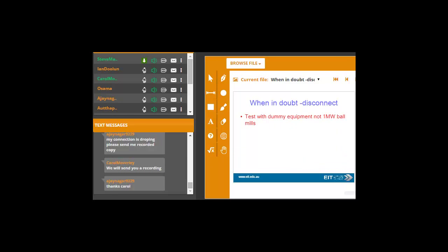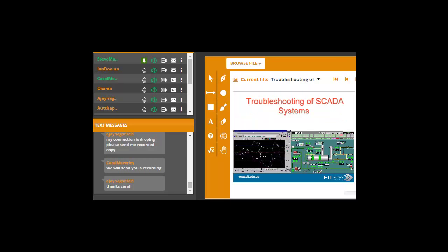So really one of the most important things is either use fiber optics or some form of optical isolation to get rid of those spikes going through. So if you have a spike coming through, it will be stopped at that point there. So fiber optic is really important to try and avoid these sort of problems. And as I said, often you'll find that that earth point there is not the same as that earth point there. So again, be wary of these little issues can be a minefield out there. So the other point I'd like to make is when you're using PLCs, if you've got any doubt about your outputs, where they're connected to, disconnect immediately. Test with dummy equipment, not 1MW ball mills. The results can be catastrophic.